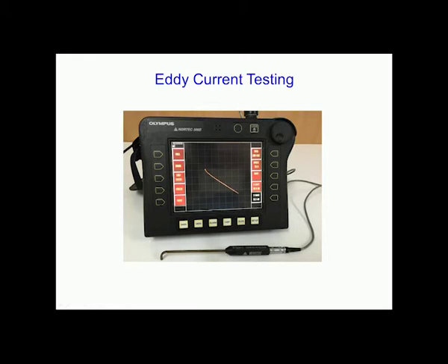And when the probe encounters any flaw on the surface, you would see a defect signal over this lift off curve, which I am going to show you in the next video. So, this is how the whole system looks, and now we are going to see the video and then see how exactly the defect signal appears on the display.